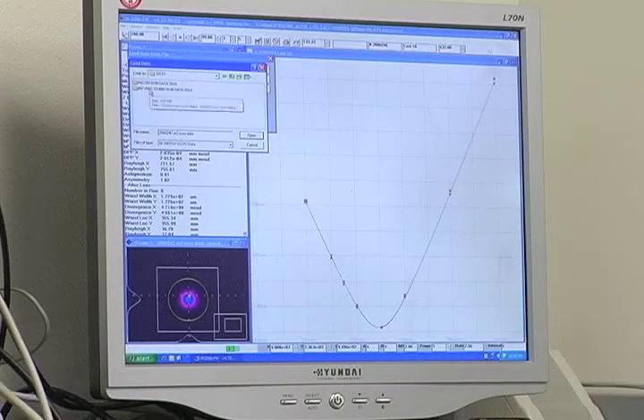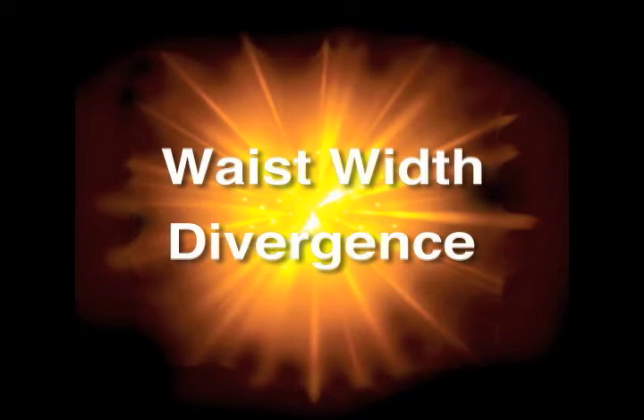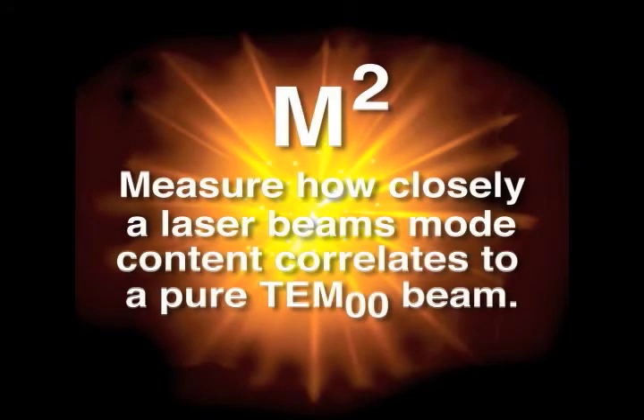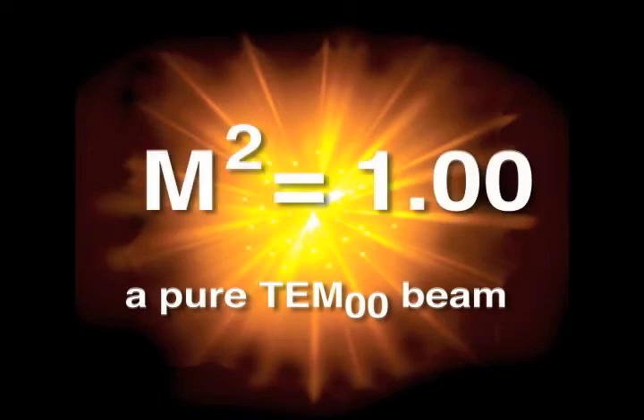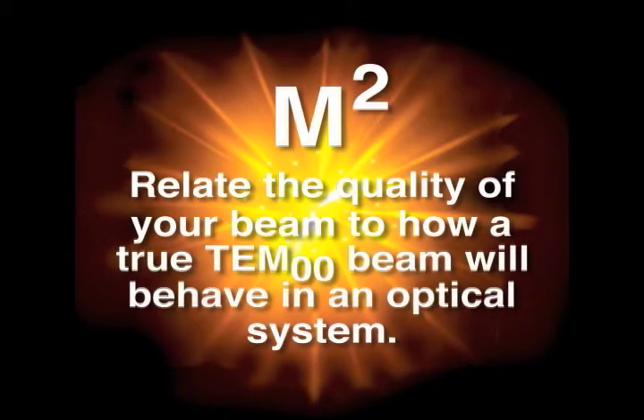Two of these values, waist width and divergence, can be used to calculate m squared, the measurement indicating how closely a laser beam's mode content correlates to a pure TEM00 beam. A laser with only TEM00 mode content has an m squared value equal to 1.00. The m squared measurement allows the user to relate the quality of their beam to how a true TEM00 beam would behave in an optical system.